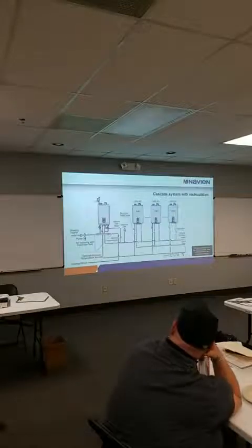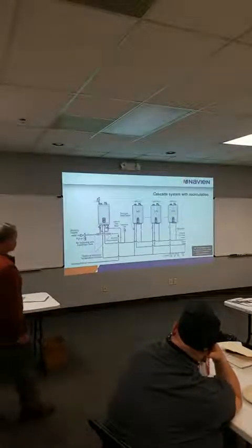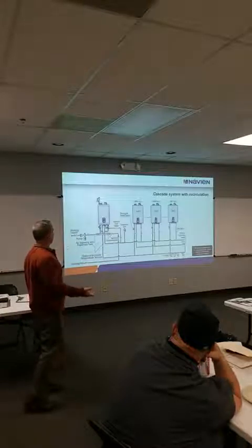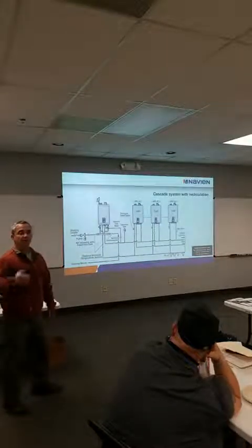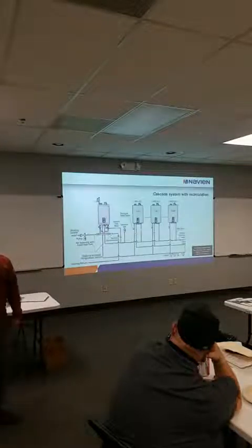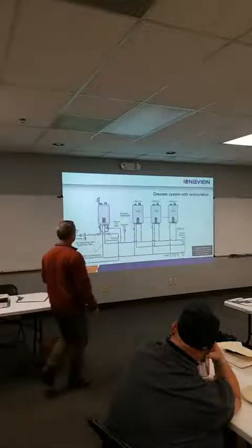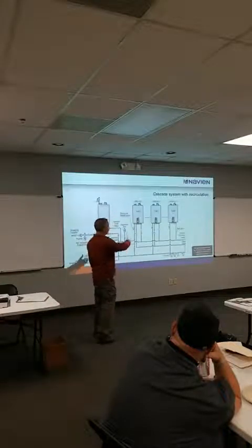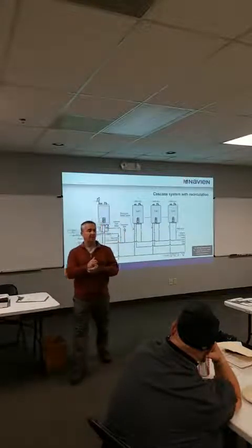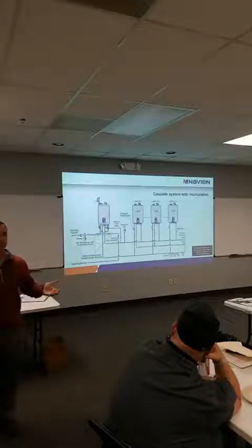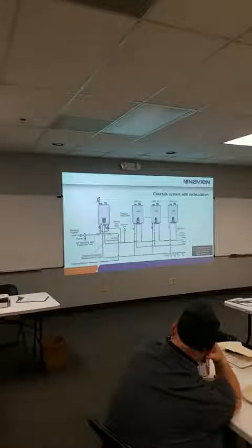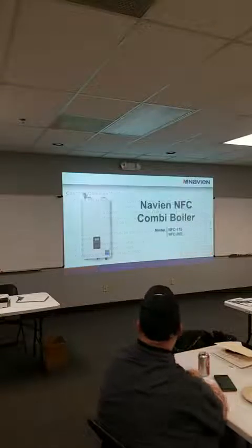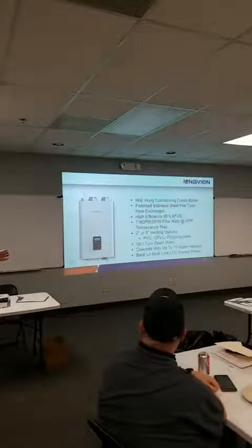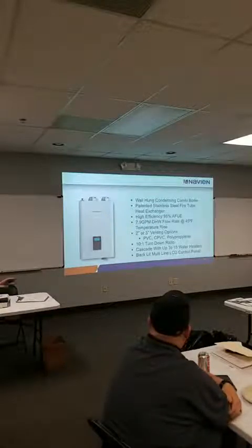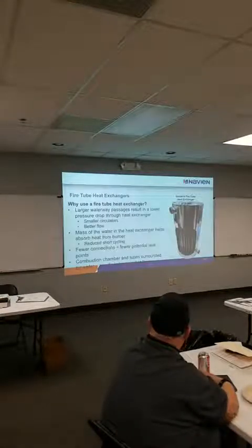Again, exclusive to Navien. It's kind of a sweet setup. You're piping everything in, and it's not hard to pipe in. You're basically adding that combi into your manifold on your hot and your cold. If you're going to do domestic recirc on this kind of system, we pull that domestic recirc back to the water heaters and not back to the combi. Not that you couldn't, but why would you? You want that combi to be your primary boiler until it has to back up on the domestic side. So, same venting picture, nothing different there. And then the NFC combi is basically everything I just talked about with the fire tube in there.